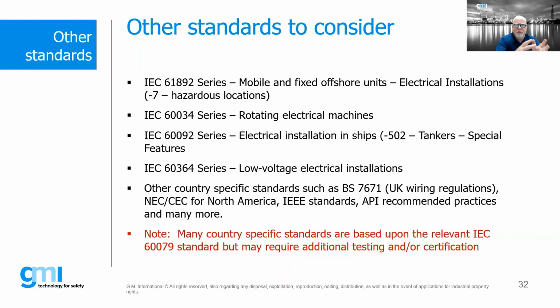502 covers tankers, special features - this could be tankers carrying LNG or being powered by LNG. This is a big issue right now because with all the clean fuels and everybody making these conversions, part of those requirements reference back to the 60079 standards, so you have to be aware of that. And then 60364 is our low voltage electrical installations. Always be aware too that there are wiring regulations within the UK, US, Canada, all over the world, so we have to make sure we're following all of that.